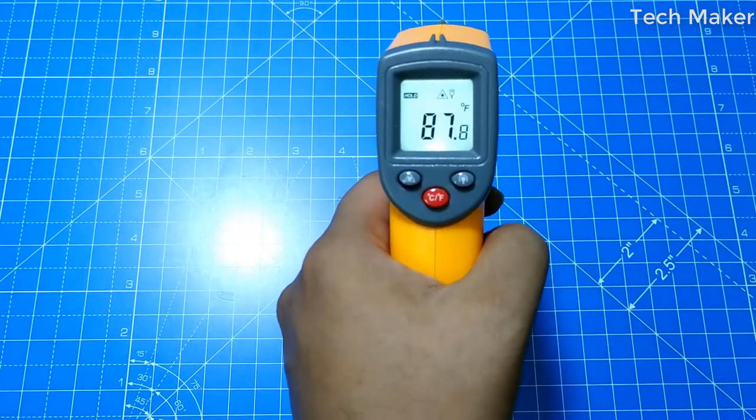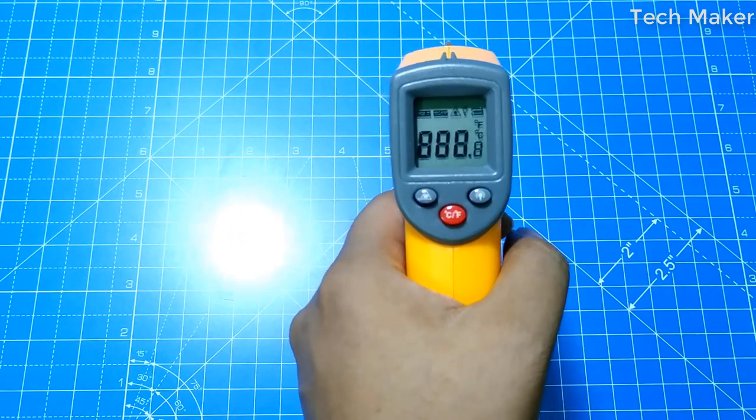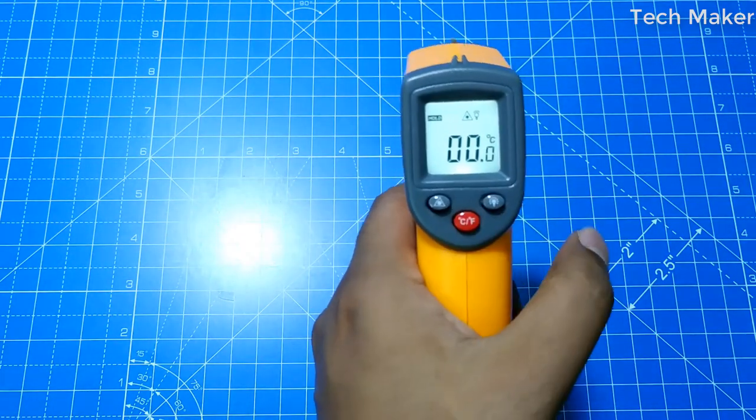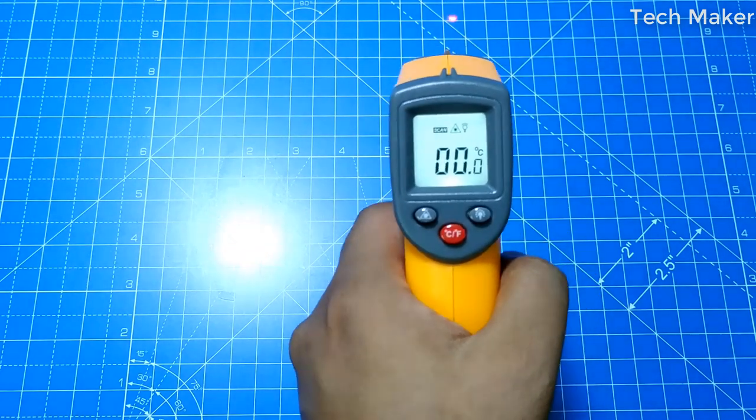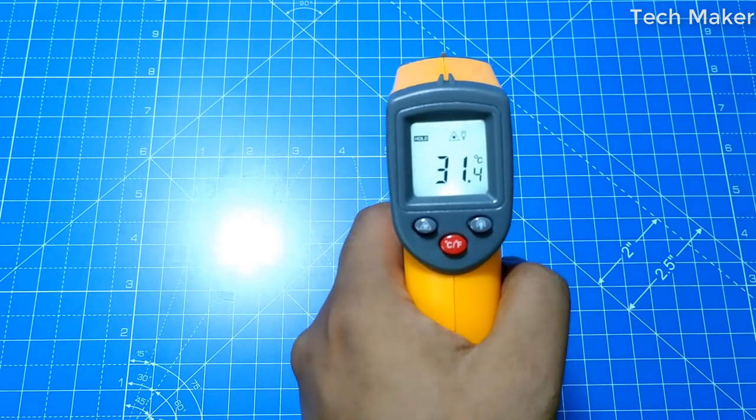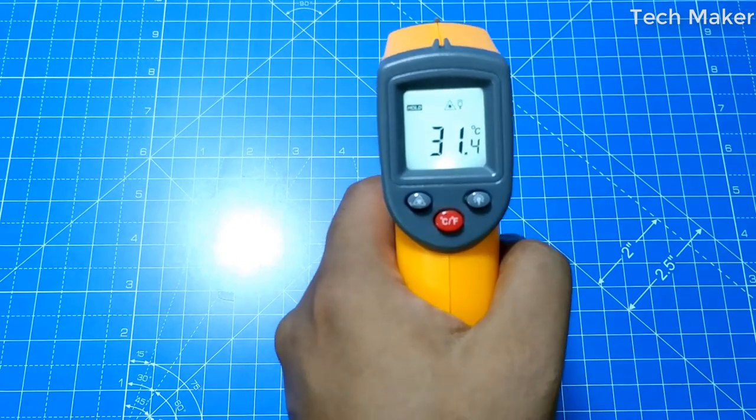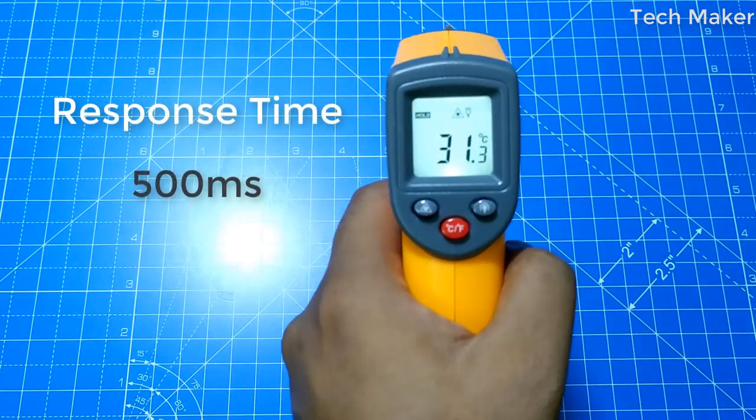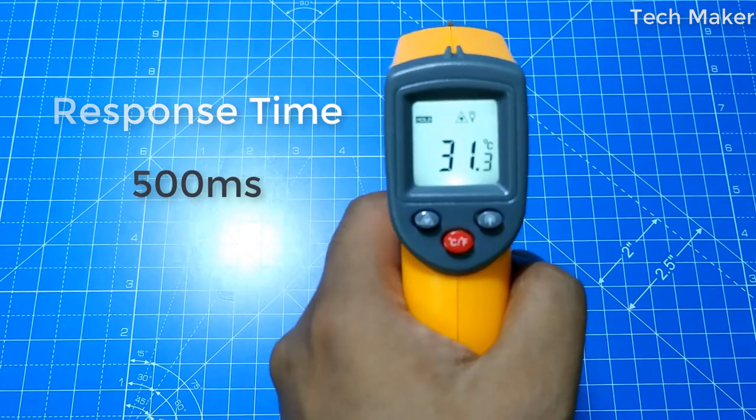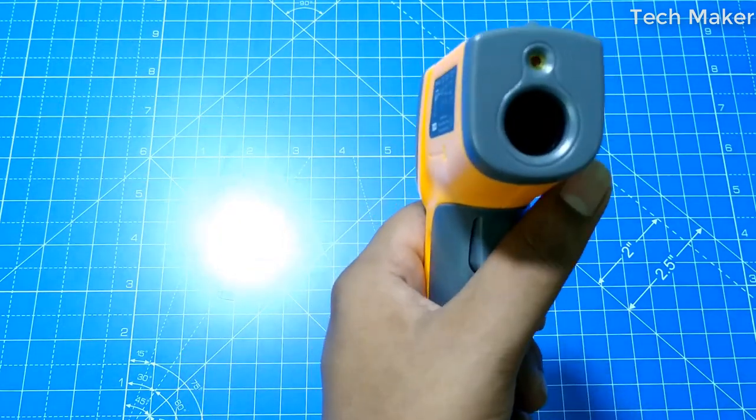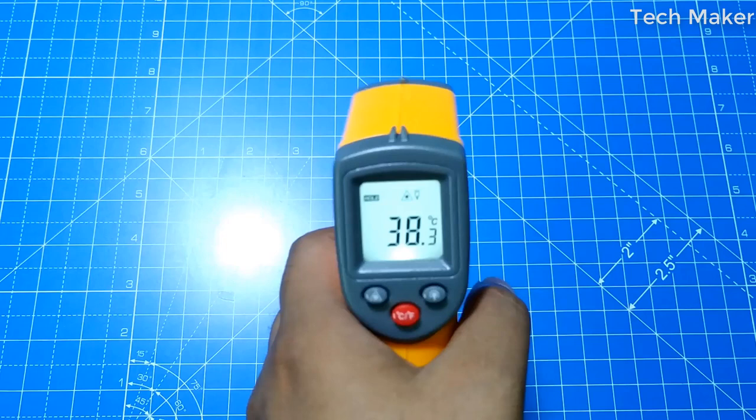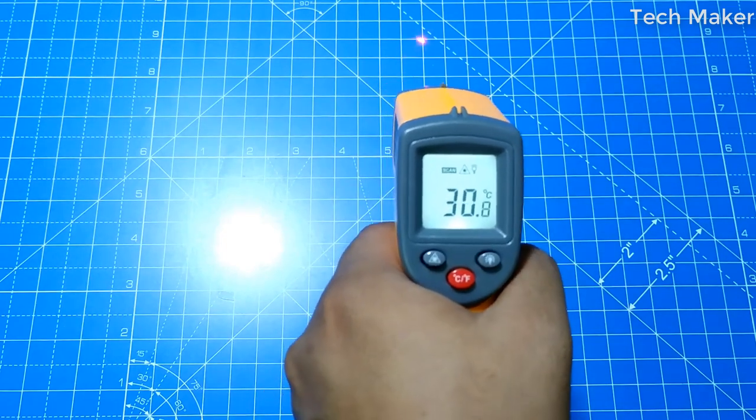And it has a faster response time so that it will get the data when you click on the trigger. And this response time as given in the specifications is 500 milliseconds. And it has a spectral response of 8 to 14 micrometers, and a distance to spot size of 12 to 1.